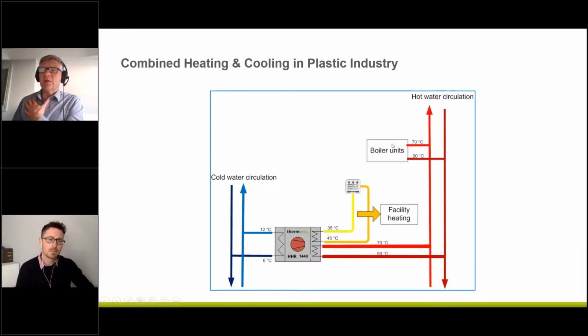Depending on the system, you can actually leave the existing boilers there to supplement. Remember the graph I showed, the very high temperatures for heating, the boiler can supplement there. So you don't have to go for a larger size, because obviously there's a capital cost for this. Let's say for 2 months or 1 month during the year you're doing an extra topping up temperature. Well, then you use the boiler there as well, and the heat pump operates in a happier, more constant loading. And it's getting better payback because it's working in those ideal conditions.